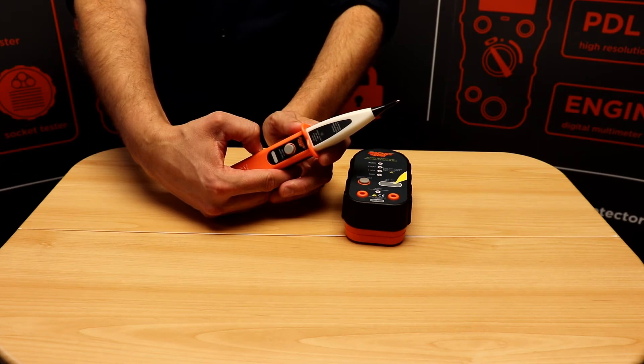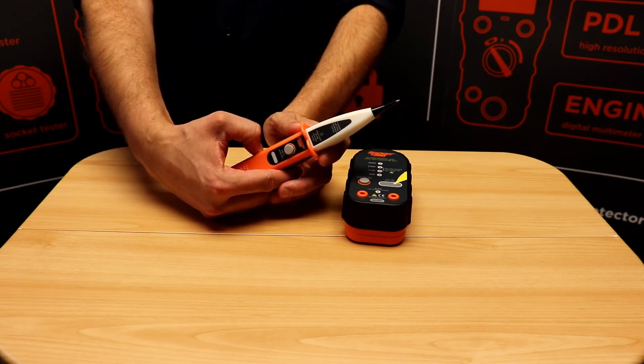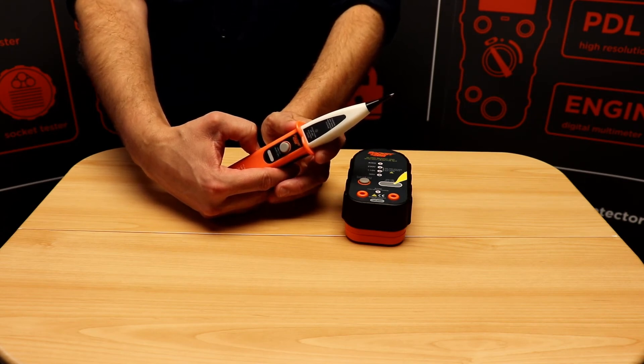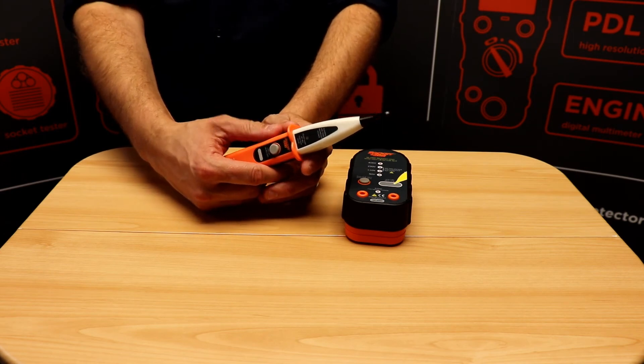When using the tester to look for voltage on extraneous metalwork, it's good practice to check the tester on a known source before and after use. In this case we're going to use the Socket & See SP400 Proving Unit.